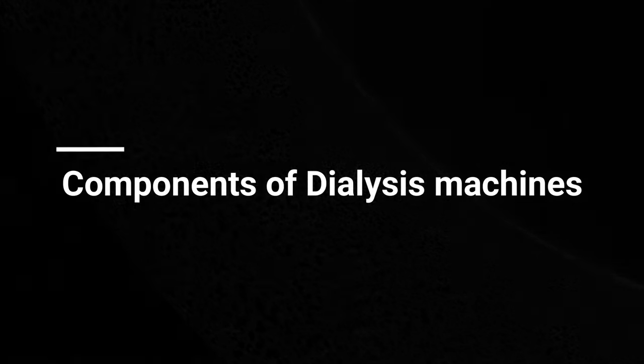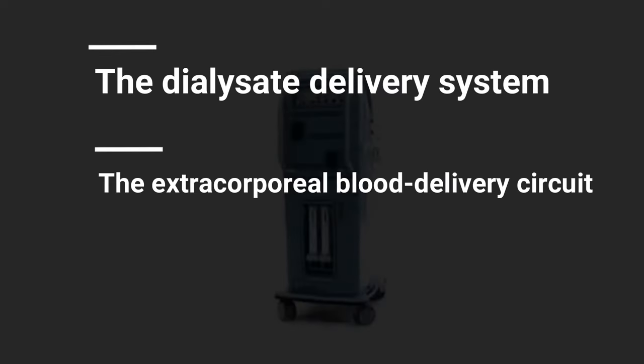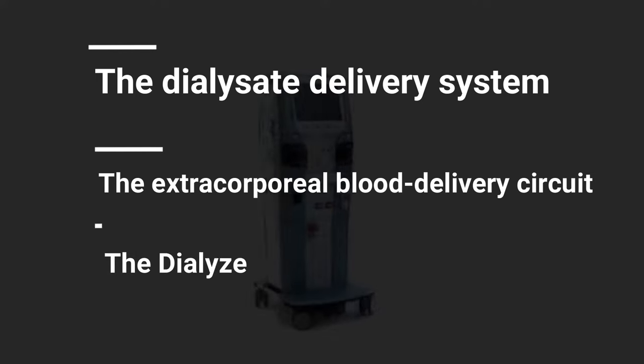Let's learn about the components of dialysis machines. Single patient hemodialysis systems can be divided into three major components: the dialysate delivery system, the extracorporeal blood delivery circuit, and the dialyser.